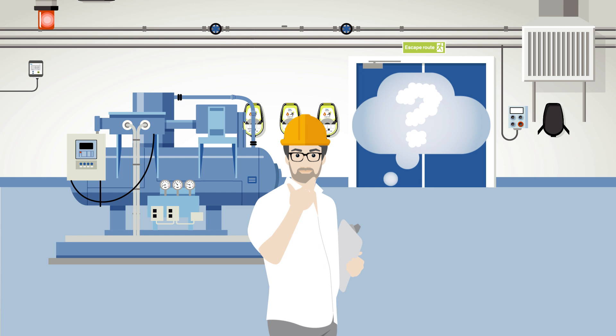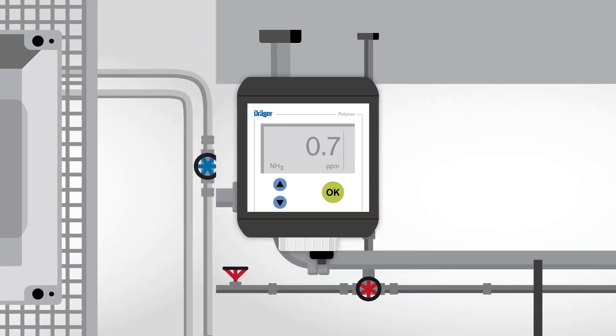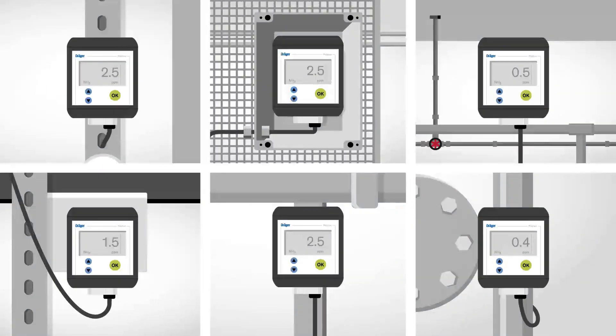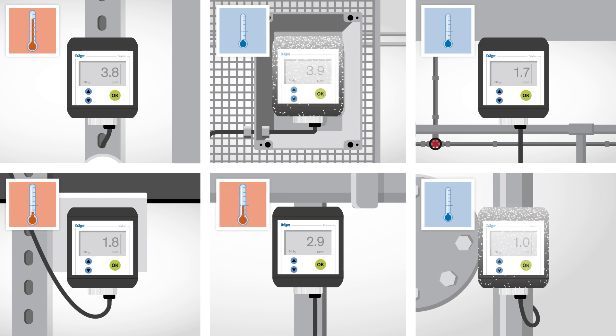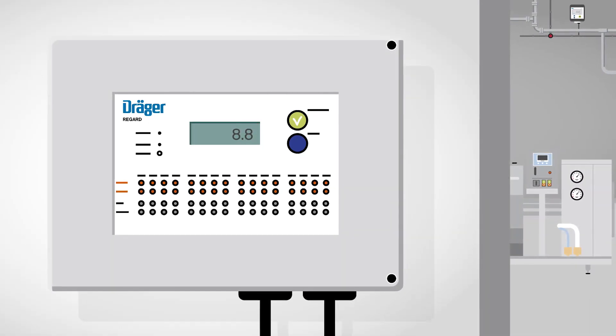So what would a system for his plant look like that could detect ammonia reliably and accurately? Fundamental to the safety of the plant is a stationary gas detection system. For early detection of gas leaks, a number of transmitters are fitted in the compressor room, the valve stations, and also perhaps the cooling chamber. Just like inside and outside the refrigerator, temperatures vary significantly in these different places. Whether warm, fluctuating, or cold, the sensors must master these rough conditions and precisely measure the NH3 concentration and respond immediately at all temperatures. The measured data is processed through a control system that interprets and translates the electronic signatures of the transmitters.